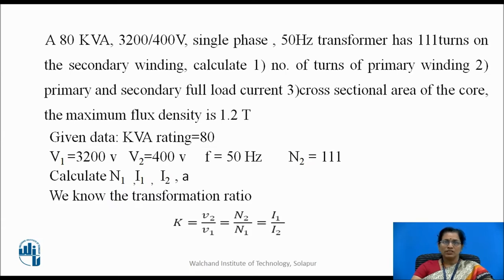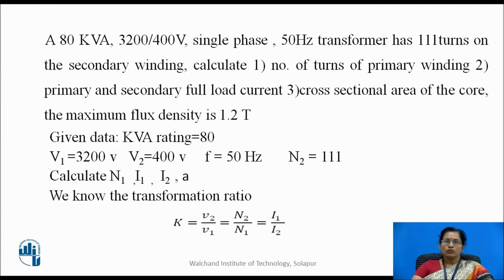A 80 kVA, 3200/400 volt, single phase, 50 Hz transformer has 111 turns on the secondary winding. Calculate: 1) number of turns of primary winding, 2) primary and secondary full load current, 3) cross-sectional area of the core, if the maximum flux density is 1.2 Tesla. Given data: kVA rating = 80, V1 = 3200 V, V2 = 400 V, f = 50 Hz, N2 = 111.